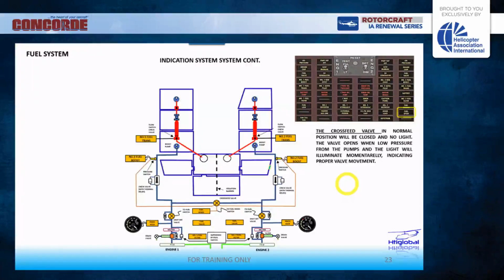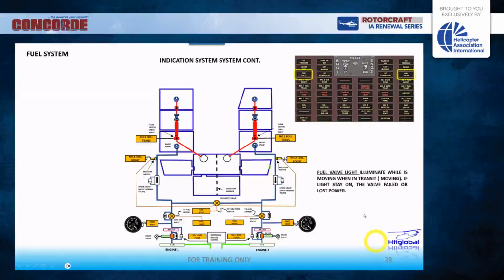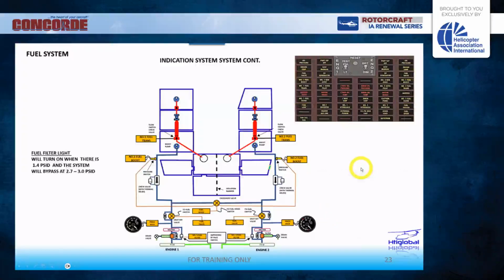Why is that? For instance, if the pilot wants to close a valve and the light stays on, it means that the valve didn't go the full travel. That means for the pilot the valve is not fully closed, or vice versa. So this valve has a way to give an indication only when in transition, and it's normal for the light to be on when you apply power to this valve. And this is what I was explaining to you, fuel valve lighting. When does that happen? Only when it's in transition.